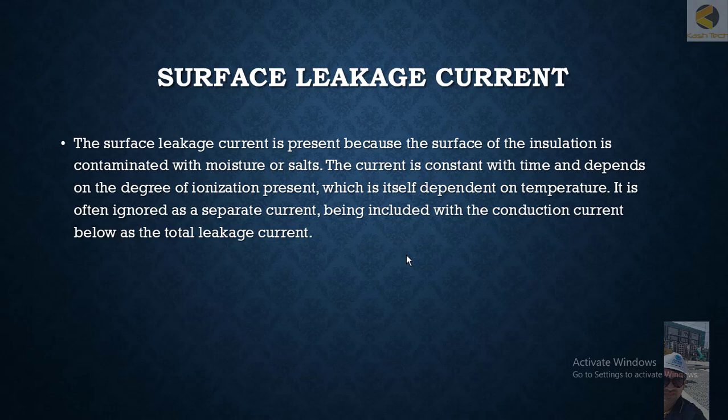The surface leakage current is present because the insulation surface is contaminated with moisture or salts. The current is constant with time and depends on the degree of ionization present, which itself depends on temperature.